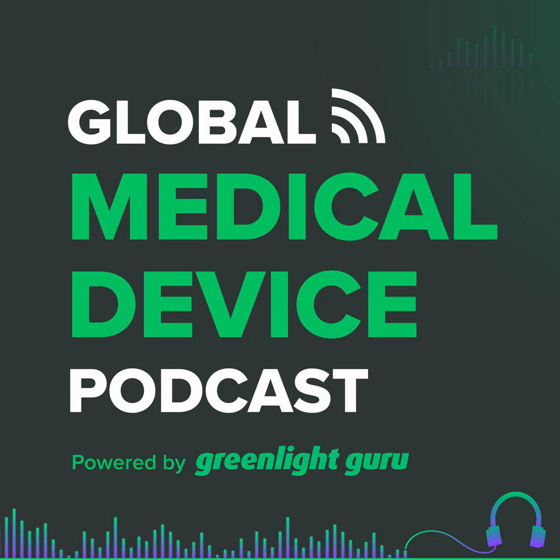If you're working on a catheter, for example, and your catheter comes in a particular length or diameter, and you're suggesting that, in the future, you're going to offer a longer catheter or a shorter catheter or a thicker or a thinner catheter, that information needs to be included in detail in the PCCP. Don't leave it nebulous like, we're planning on making the catheter a little longer, but how much longer, quite frankly, we don't know what that's going to be.